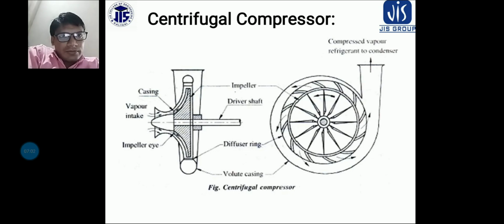In the case of a single stage centrifugal compressor, the compression ratio that an impeller can develop is limited to about 4.5. When a high compression ratio is required, multi-stage centrifugal compressors with intercoolers are employed. One more important thing: the centrifugal compressor has no valves, piston, and cylinder.